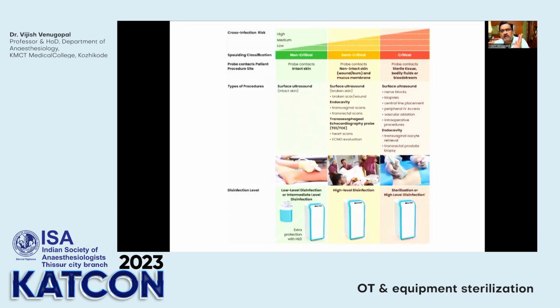Now, the same equipment can become critical, non-critical, or semi-critical based on where it is used. For example, your ultrasound probe. All of you would be using the ultrasound probe in the theater. Suppose for just scanning a patient, you do a scout scan on the intact skin. You just require a low level or an intermediate level of disinfection. But suppose the same ultrasound probe, like a TE probe, is being inserted. The TE probe has to have a high level because it is contacting the mucous membrane of the esophagus. Now, suppose you are using the same ultrasound probe to put in a central line or give a nerve block. Ideally it should be sterile, or a high level disinfectant should have been used. Like nowadays we use a sterile cover on the ultrasound probe, so it becomes a critical object. So the same probe becomes non-critical, semi-critical, and critical depending on the situation in which it is used.